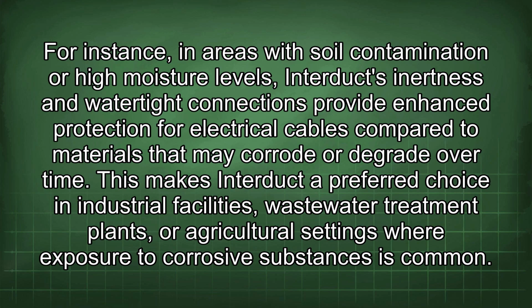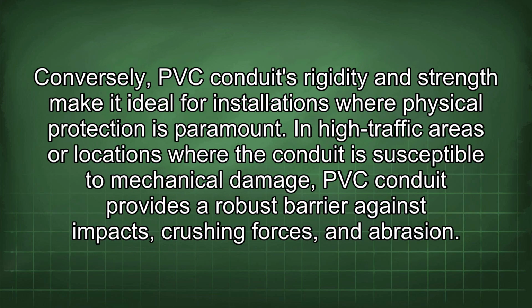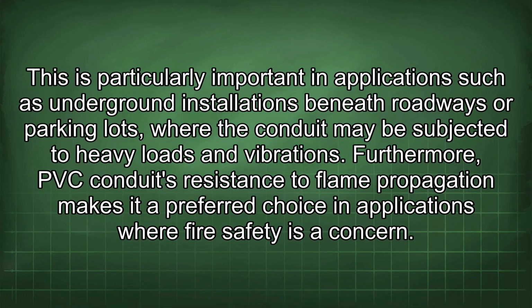Conversely, PVC conduit's rigidity and strength make it ideal for installations where physical protection is paramount. In high-traffic areas or locations where the conduit is susceptible to mechanical damage, PVC conduit provides a robust barrier against impacts, crushing forces, and abrasion. This is particularly important in applications such as underground installations beneath roadways or parking lots, where the conduit may be subjected to heavy loads and vibrations.